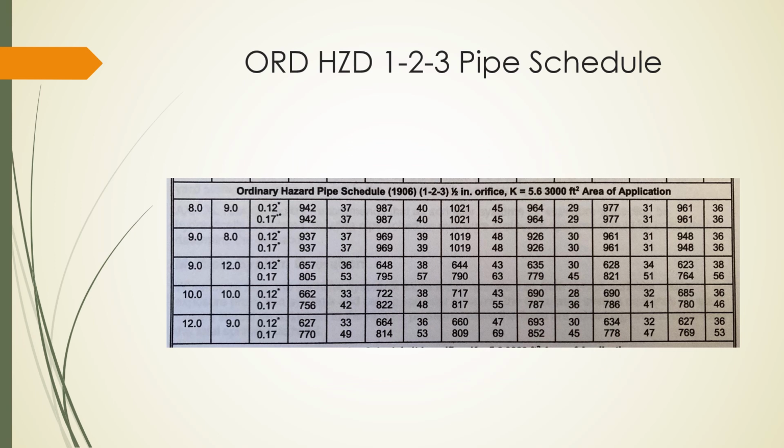On that same page is the 123 system with the 3/4 inch end lines that we talked about, the 1905 to 1940 system. Again, the same thing, K 5.6 head, half inch. It's what we expect to see in these older systems. And there's no difference than the above with the line, head spacing, density, and those numbers providing you with some sense of what the water and pressure requirement will be to meet the adequacy of an occupancy.